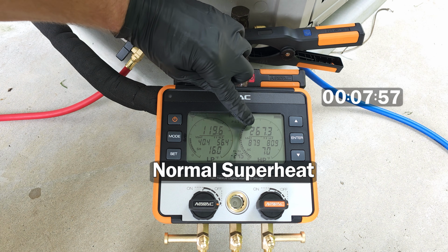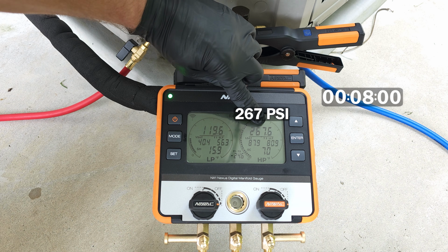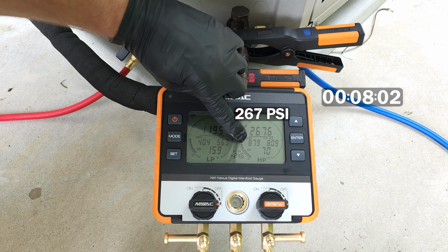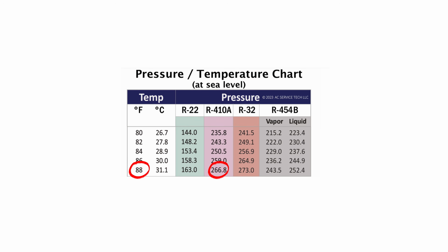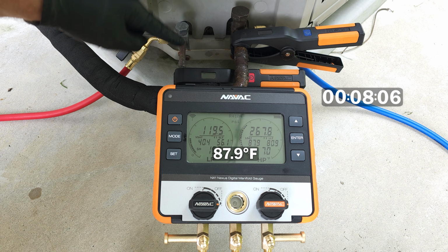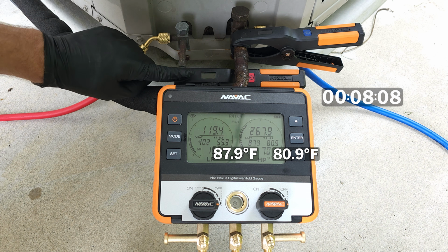And if we measure on our high side, it's 267 psi. We convert that to a saturated temperature for R410A in the outdoor coil, it's 87.9. We also have a line temperature right here of 80.9.